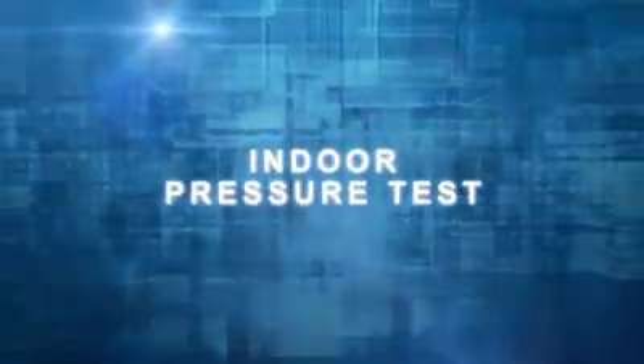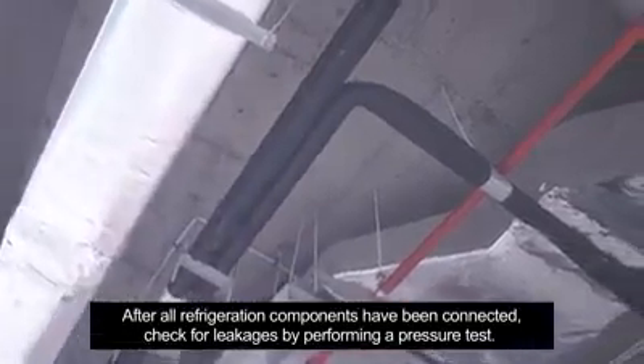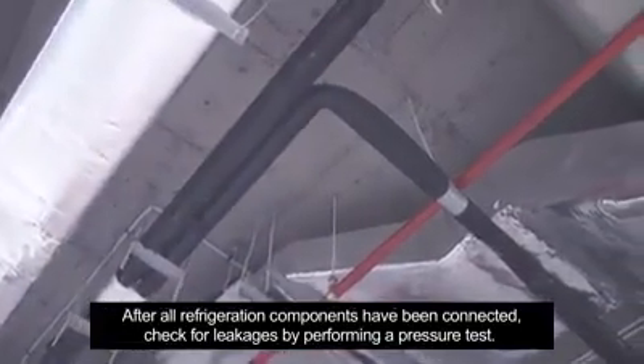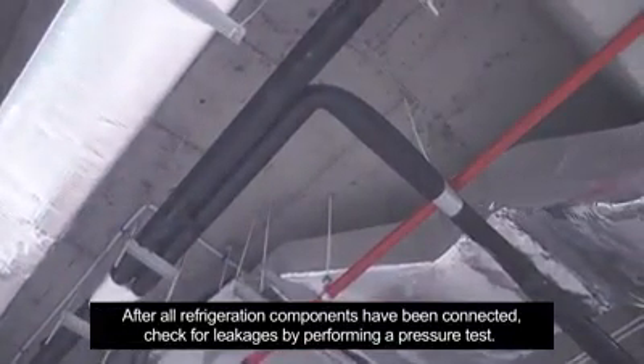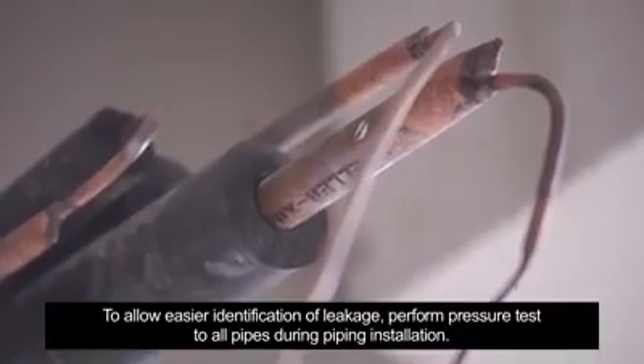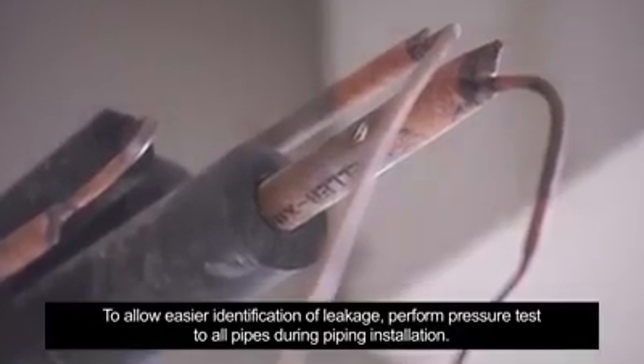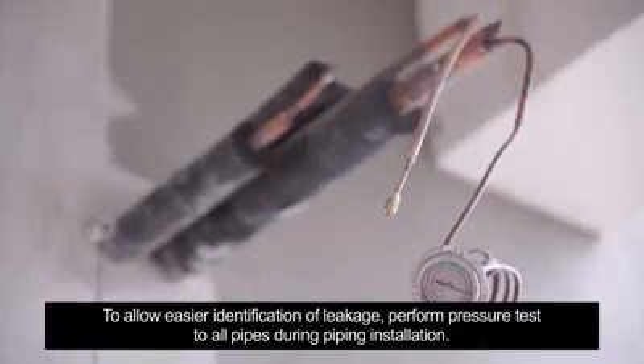Indoor pressure test. After all refrigeration components have been connected, check for leakages by performing a pressure test. To allow easier identification of leakage, perform pressure tests to all pipes during piping installation.